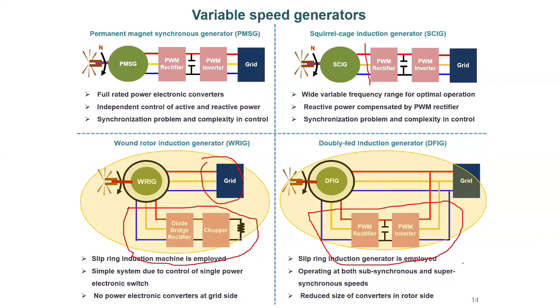In the doubly fed induction generator, you see that the power converters are employed on the rotor side. That means only the slip power rating is the rating of the power converters. So the output of the stator is connected to the grid. So it is a slip ring induction machine. The generation is possible at both subsynchronous speed and supersynchronous speed. The converters on the rotor side are reduced in size.